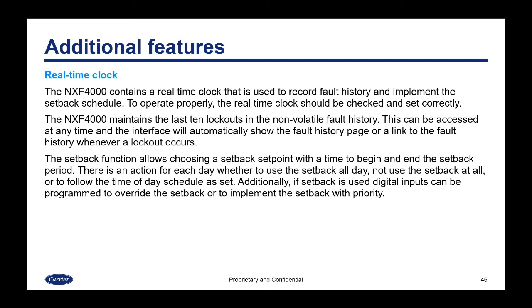The setback function allows choosing a setback set point with a time to begin as well as end the setback period. There's an action for each day, whether to use the setback all day, not use the setback at all, or to follow the time of day schedule as set. Additionally, if setback is used, digital inputs can be programmed to override the setback or to implement the setback with priority.